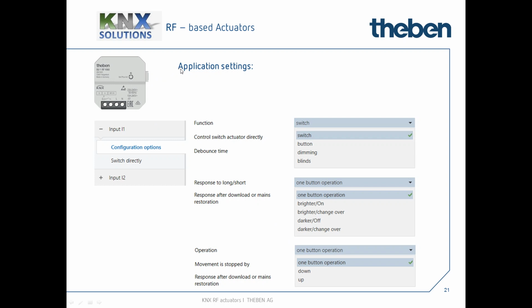So what are finally the functions to be used here? Basically, as a default, you get this binary input or actuator set so that the binary input switches directly. That means without any programming, you affiliate or link a push button to these binary inputs, and with this push button, when we talk about switching, you can switch on or off without any programming.